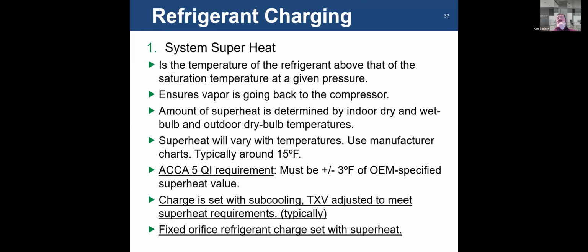So, other methods of setting a charge. System superheat. What is it? It's the temperature of the refrigerant above the saturation temperature at a given pressure. It ensures vapor is going back to the compressor. You can't compress a liquid; you need vapor to compress. The amount of superheat is determined by the indoor dry and wet bulb and the outdoor dry bulb temperature. This would be given by the manufacturer, and it will vary depending on those temperatures. It's typically around 15 degrees, and depending on your outdoor and indoor conditions, it may be different. ACCA 5 QI says that you must be within plus or minus 3 degrees of the OEM specified superheat value.